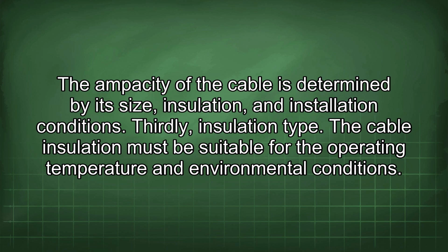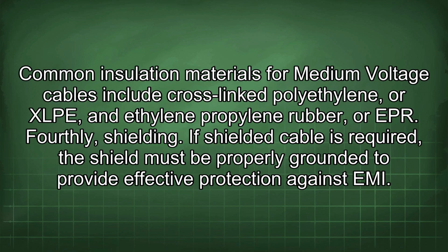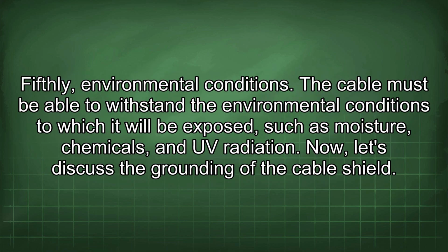Thirdly, insulation type. The cable insulation must be suitable for the operating temperature and environmental conditions. Common insulation materials for medium voltage cables include cross-linked polyethylene, or XLPE, and ethylene propylene rubber, or EPR. Fourthly, shielding. If shielded cable is required, the shield must be properly grounded to provide effective protection against EMI. Fifthly, environmental conditions. The cable must be able to withstand the environmental conditions to which it will be exposed, such as moisture, chemicals, and UV radiation.